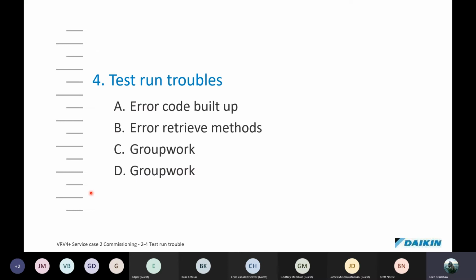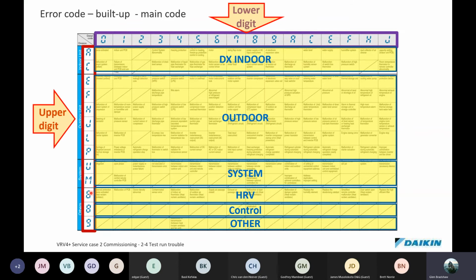Right, test run troubles. So let's have a look at the error code buildup. This is where this course starts to fit into the advanced VRV fault finding. Now we've got an overlap between that and this course, so it's important that the installation technicians also get to know a bit about this. Often there's a difference between a service technician and an installation technician, but it's always important that the installers also have a fair idea of how the fault codes are built up. Many of you might be familiar with the old Daikin cardboard fault finding chart that we used to give out at training.